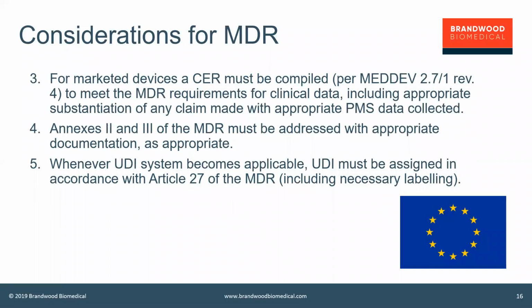Next one to mention here, and we've touched on this before, like I said, we had a webinar on this completely 2 months ago on the CER, but the CER is becoming more and more scrutinized by the notified bodies, not only in the ramp up towards MDR, but we know it will be when the MDR is implemented. So really ensuring that the CER is completed per MedDev 2.7/1 Rev 4 so that your clinical data is captured.